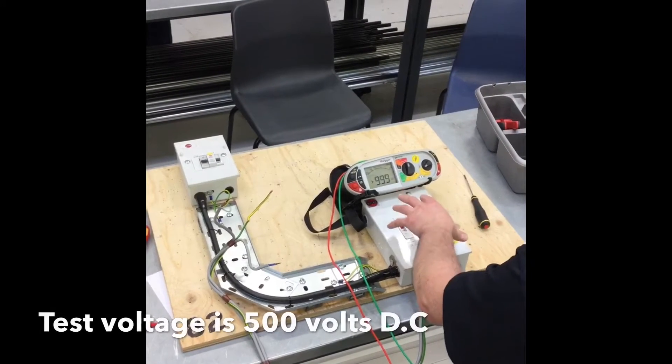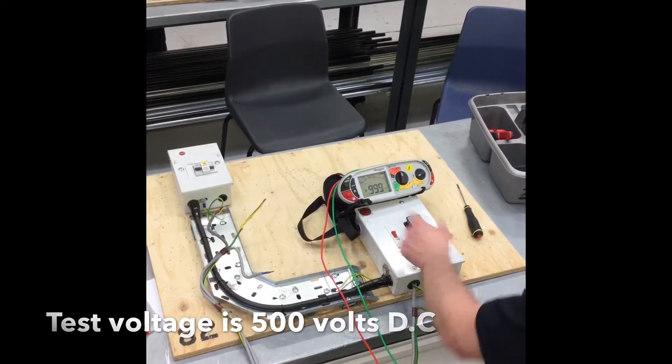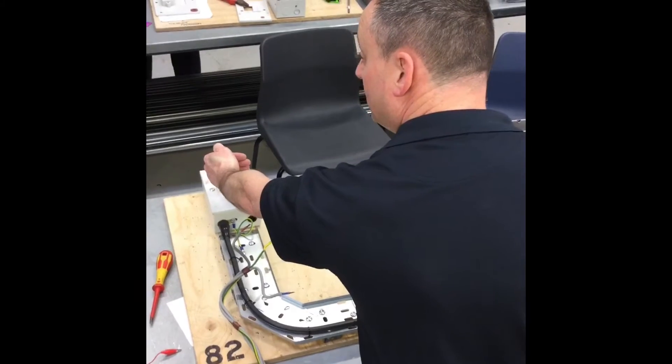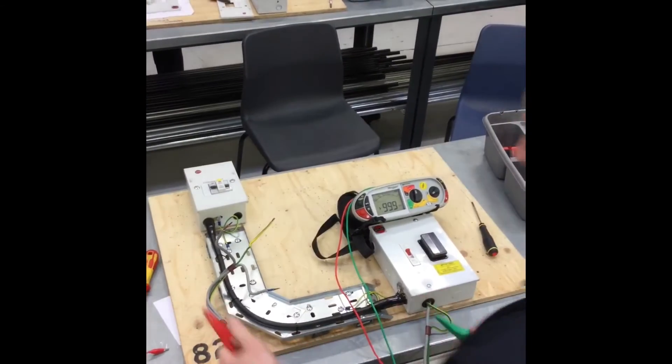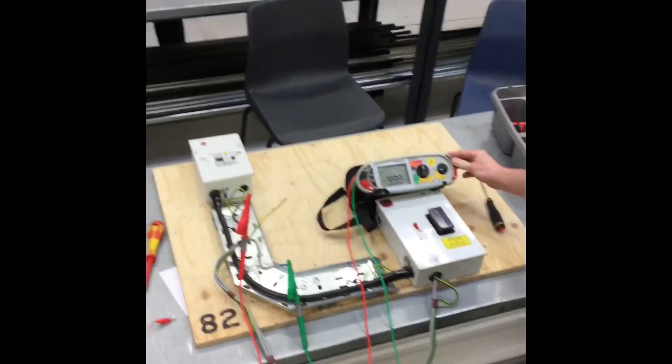damaged during this test when we pass 500 volts through it. Main switch is on, the fuse is installed, and we're going to do the test from the tails up to the top of the main switch of the sub main circuit. Connect between live conductors, press and hold.